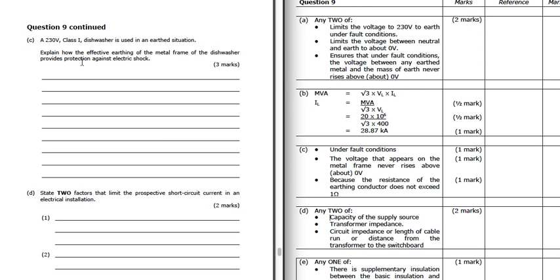A 230 volt class 1 dishwasher is used in an earthed situation. Explain how effective earthing of the metal frame of the dishwasher provides protection against electric shock. So it's going back to this, that if there is a fault, because it's earthed, it will make sure that the voltage on the frame never rises above this 0 volts, because the resistance of the earthing conductor does not exceed 1 ohm. So as long as we keep this earthing conductor to a low resistance, then this voltage on the frame never gets above 0 volts. It's when we've got a very high resistance in the earthing conductor, and we've seen that in some of the calculations, that the protective device doesn't operate, we get current flowing and we get a shock hazard.